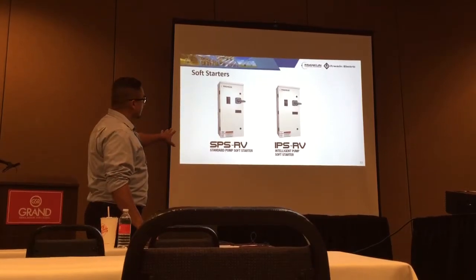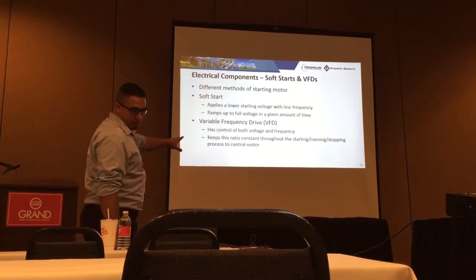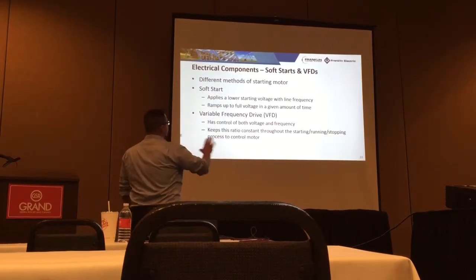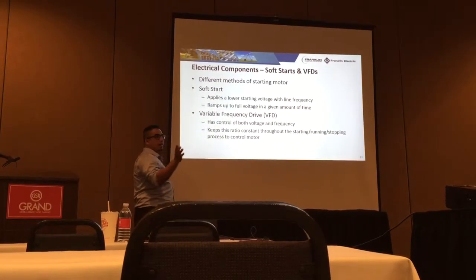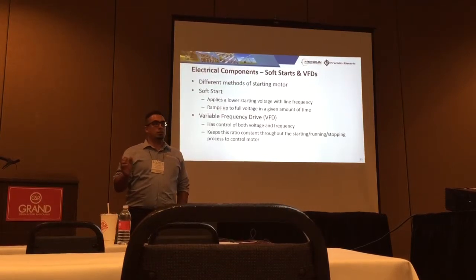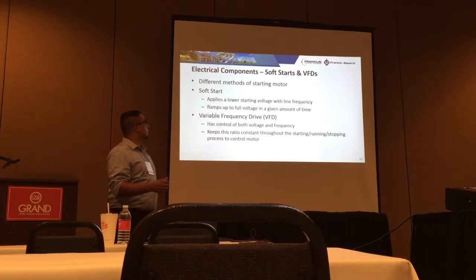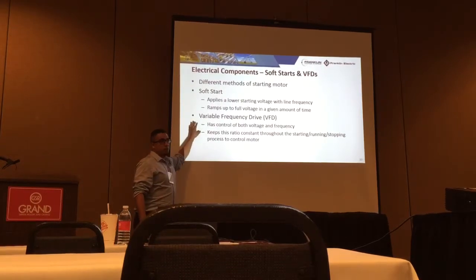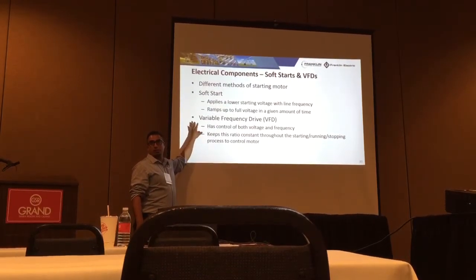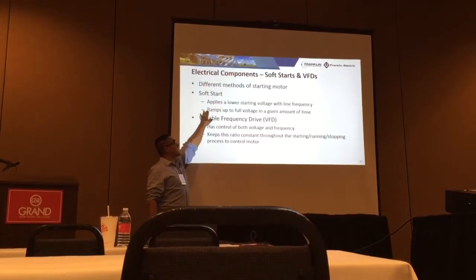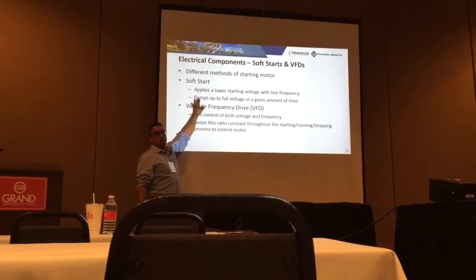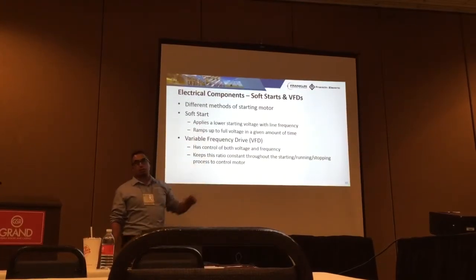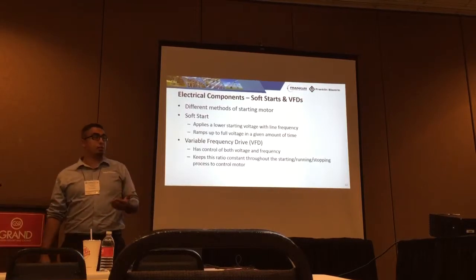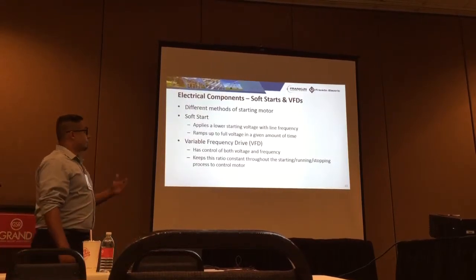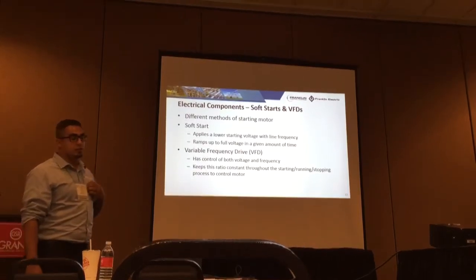So going over to soft starts now, we're looking at differences with and across the line. So who has used soft starts? Good, good, good. Does everyone know the difference between a soft start and a variable frequency drive, VFD? Why the two starts are completely different? You can almost tie this into part wind starts, wye-delta starts. All it's doing is reducing the inrush, but it's still hitting with a 60 Hertz cycle. The drives, when I get to the end portion of it, do it a little bit differently.